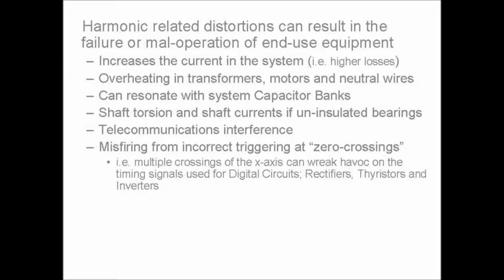But when it is there, I suppose the first thing is you've got more currents in the system, and everybody knows excess currents in the system can lead to higher losses, the I2R losses, so that's not good. You end up with overheating in your transformers, your motors, maybe neutral wires if you have neutral wires for your transformers. You might need to reconsider your specifications for them. Worse again, it can resonate with the system capacitor banks. There's a lot of cap banks around the system in various locations for voltage support. Any kind of resonance with them can cause your cap banks to fail, which isn't particularly good.